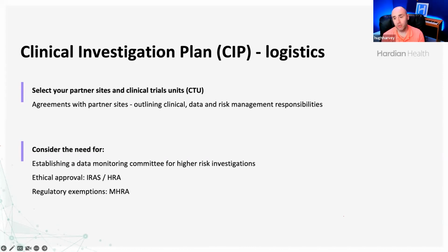And this is done in the UK through the IRAS platform, which is run by the HRA. And then, which we will explain in a little while, you will need an exemption from the MHRA. So you need to write to the MHRA and say, we would like to conduct a pivotal clinical investigation of a non-UKCA or CE marked medical device. Can we have approval? And they will ask to see your CIP, your intended use, your literature review, your feasibility study data, and your analytical validity data. So you will need that documentation in order just to get a clinical investigation off the ground.